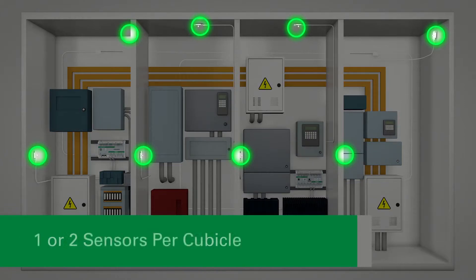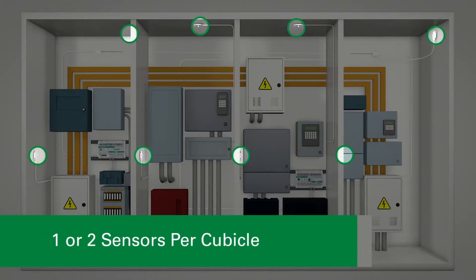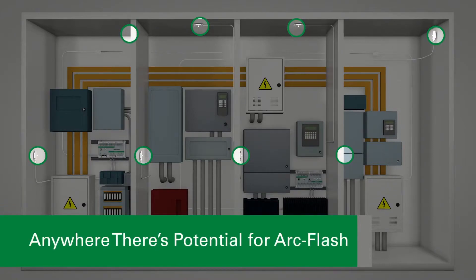Littelfuse recommends mounting one or two sensors per cubicle to cover all horizontal and vertical bus bars, breaker compartments, and anywhere there is potential for an ArcFlash.